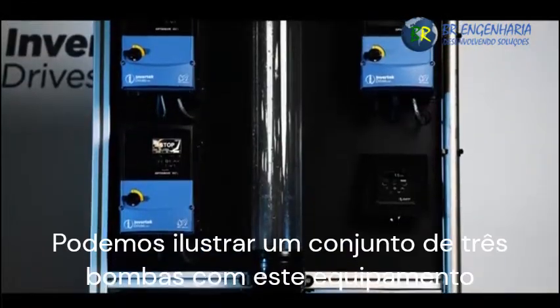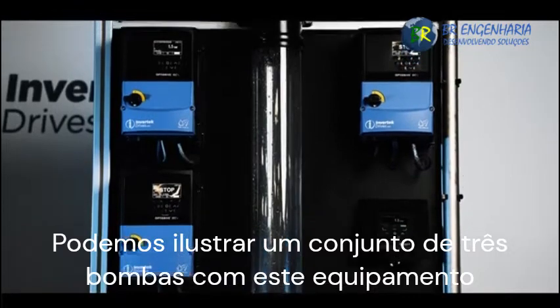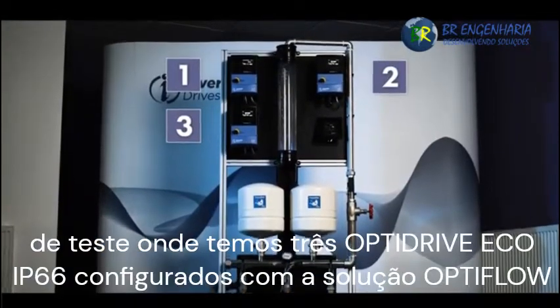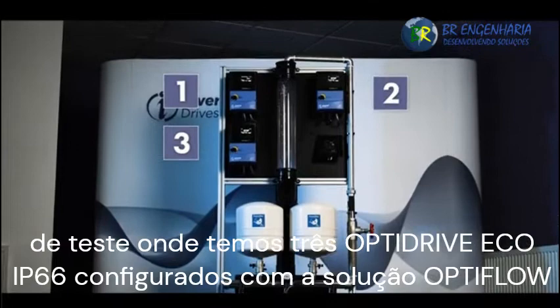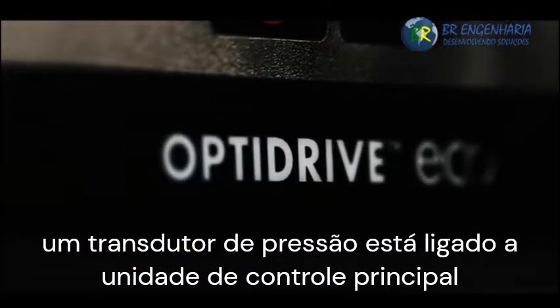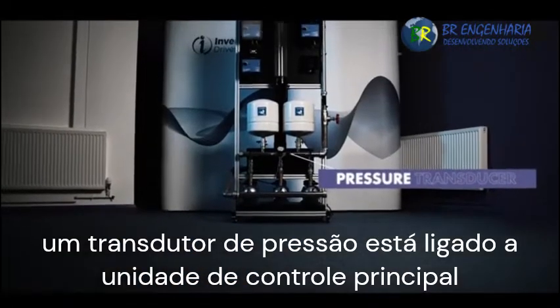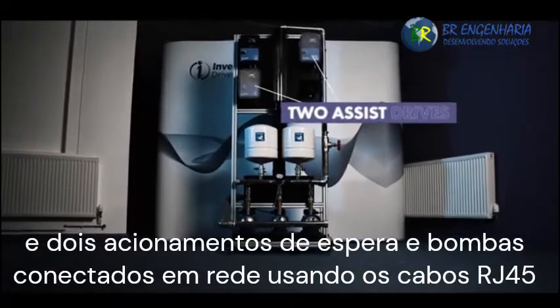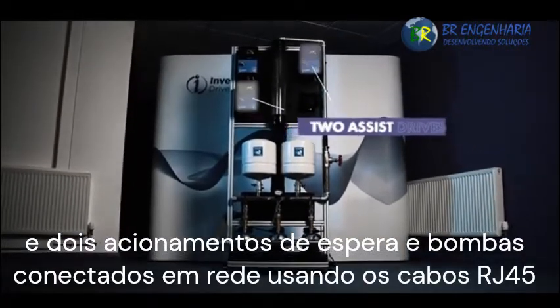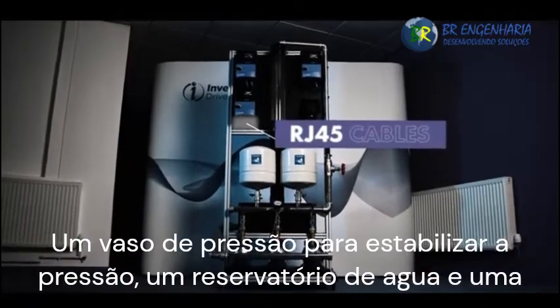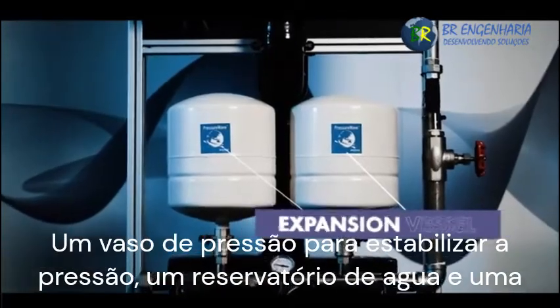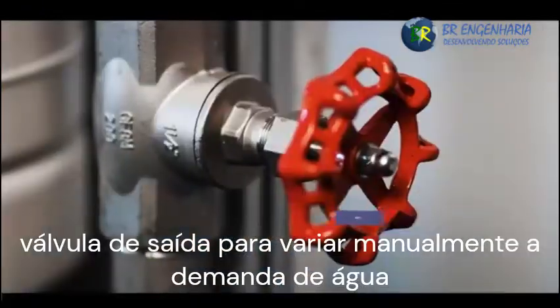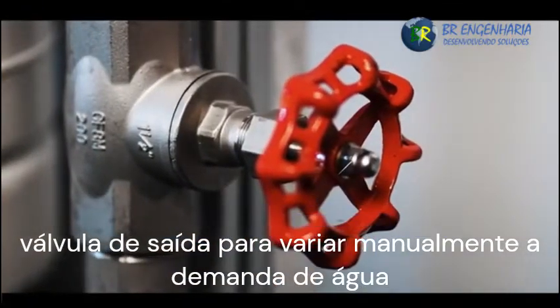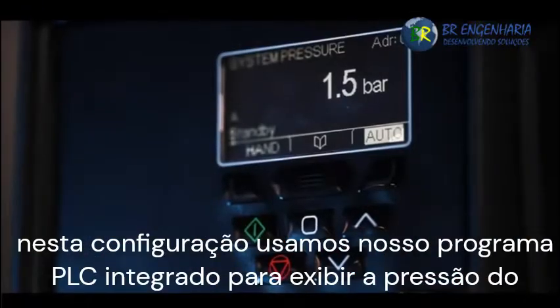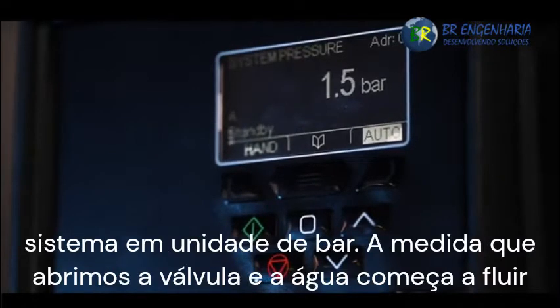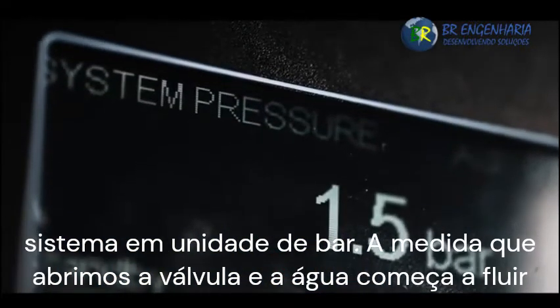We can illustrate a 3-pump booster set with this test rig, where we have 3 Optidrive Eco IP66 outdoor rated drives configured with our OPTIFLOW solution. A pressure transducer is connected to the master controller drive, and 2 assist drives and pumps with all drives networked together using the RJ45 cables, an expansion vessel to stabilize the pressure, a water tank or reservoir, and an outlet valve to manually vary the water demand. In this setup, we have used our onboard PLC program to display the system pressure in units of bar.